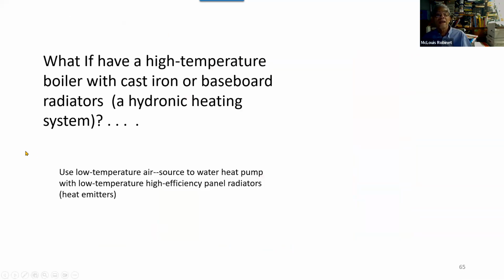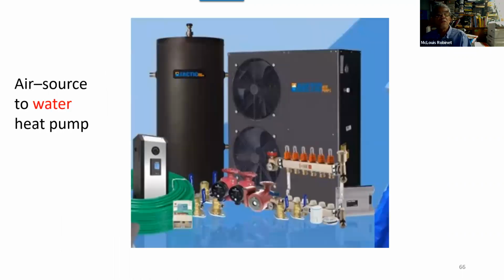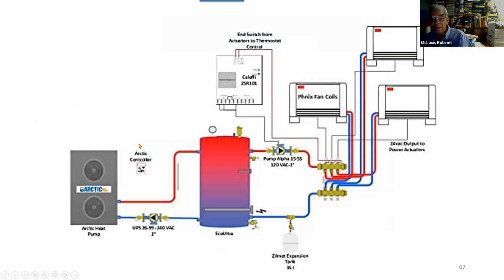But what if you had a high temperature boiler, say with a cast iron radiator hydronic system? What are your options? Instead of using an air to air heat pump, which are all the ones we talked about so far, you could use an air source to water heat pump. You would put one coil in this tank, bring it up to the temperature you want, and then use these tubings to connect that to the radiators. Use these pumps to pump water through the radiators. So something like this: the heat pump, a buffer tank, and you provide the different radiators.